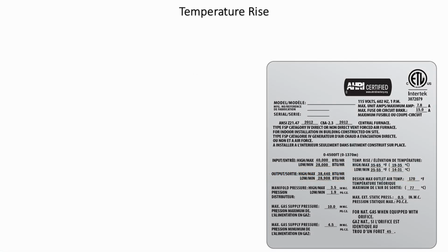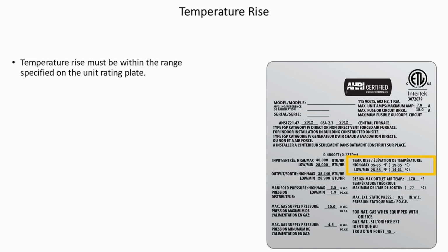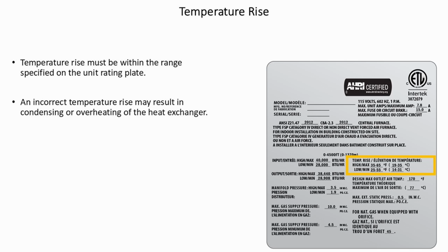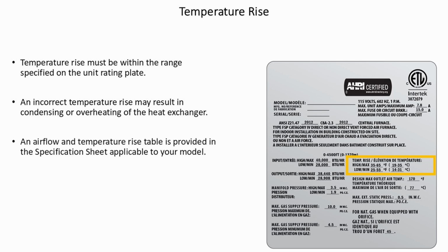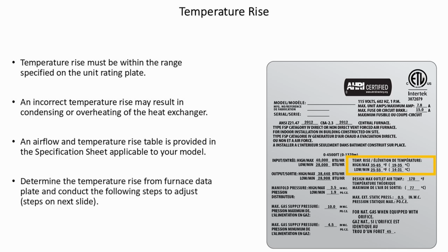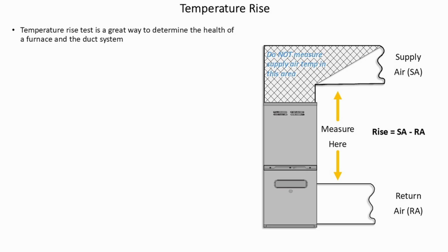Temperature rise. Temperature rise must be within the range specified on the unit rating plate. An incorrect temperature rise may result in condensating or overheating of the heat exchanger. An airflow and temperature rise table is provided in the specification sheet applicable to your model. Determine the temperature rise from the furnace data plate and conduct the following steps to adjust. Temperature rise is a great way to determine the health of a furnace and the duct system.